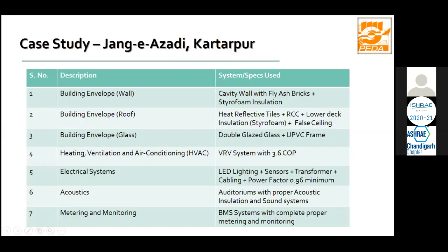For the building envelope roof, you can use heat reflective tiles over the RCC, reinforced cement concrete - what we call 'lintel' in Hindi - plus lower deck or above deck insulation. In this building, they used lower deck insulation, meaning insulation below the RCC, plus a false ceiling.